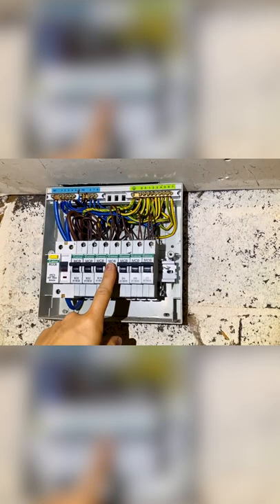So these three circuits are kind of suspect. What I've done now is turned all the circuits back on apart from the faulty circuit, and I'm going to go and check around the building and see what's not working — then I'll know what that circuit actually does.